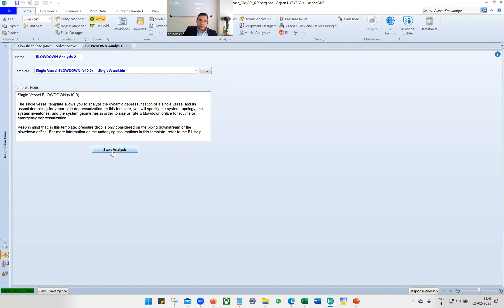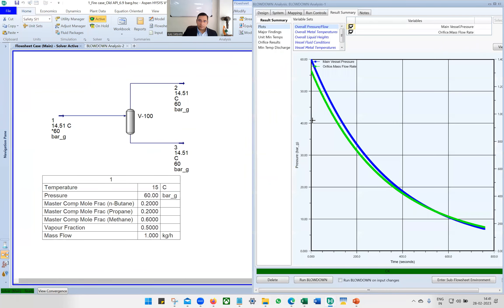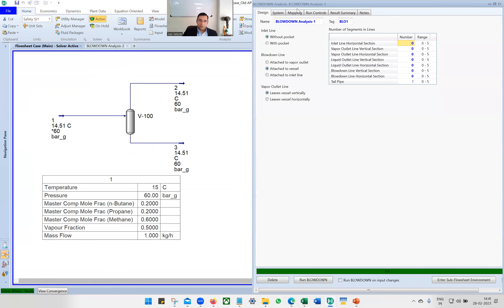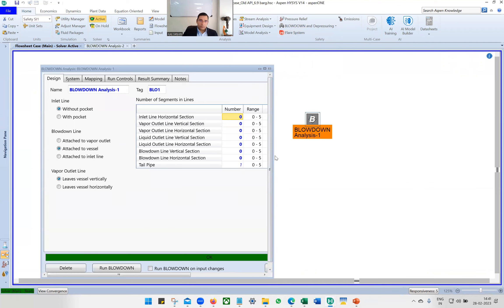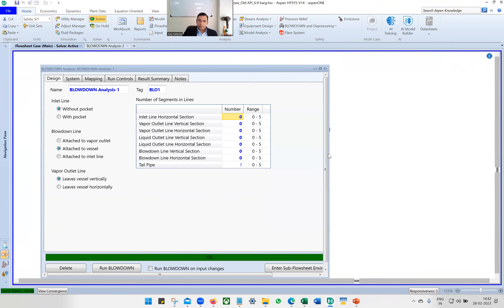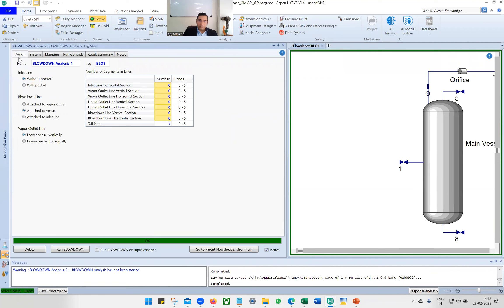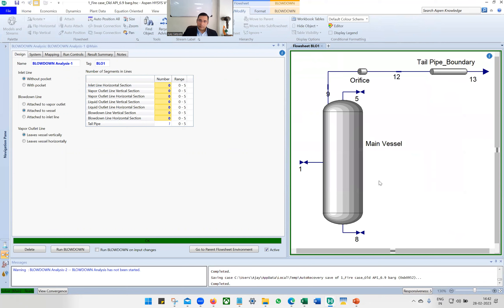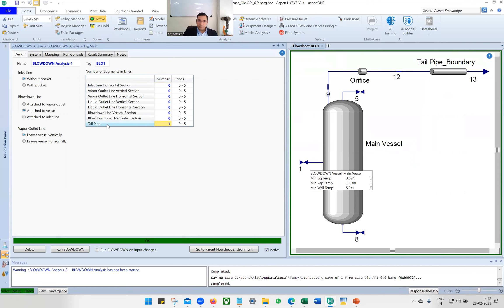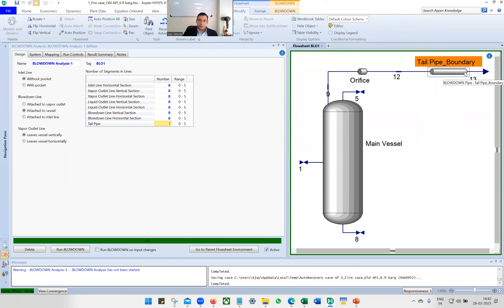Click Start Analysis and you get the blowdown analysis window. The first thing to do in Design is to make the inlet line to blowdown line horizontal section length zero. We are only going to consider the volume occupied by the main vessel and not any piping volume, to keep things simpler. However, we are going to consider a tailpipe, so we keep the tailpipe as one.